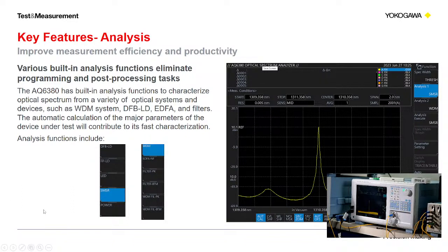So next thing we want to talk about is the different analysis routines that are built in. So this is built in for your convenience. There's a number of different analysis routines, just like our 70 series models and many models before this, for WDM analysis, DFB analysis, EDFA analysis and filters, and there's over 10 or up to 13 analysis routines that are built in.